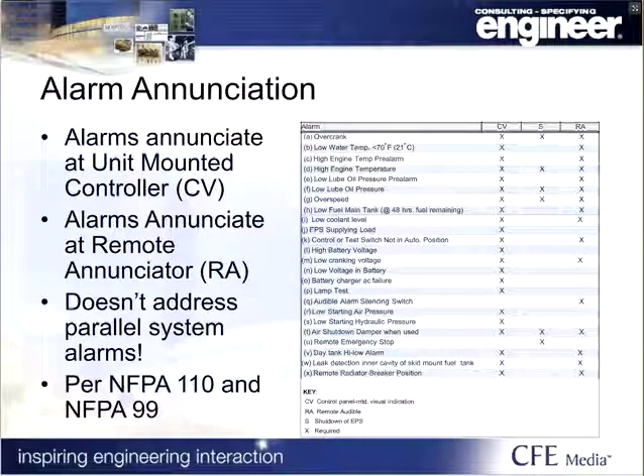Next step is alarm annunciation. NFPA 110 has a huge list of code-required alarms that are required to be displayed first at the unit controller, so on the generator, and then also at a remote location. It is written around a single generator installation. It's not written around a parallel system, so there are some alarms that are good practice that are related to parallel systems that are not necessarily in the list. And then there's a couple of items in the list that aren't necessarily applicable to every system, like, I think, an air start, air shutdown damper.